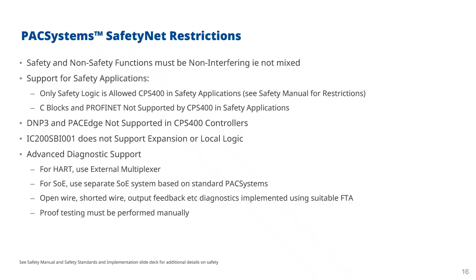If you want to do sequence of events, we do have some first up reporting capabilities inside the function blocks, but they're not normally timed. So if you wanted a full SOE system to do sequence of event reporting, then you would have to take your inputs into a separate SOE system, and that could be based on our standard PACSystems controller. Open wire, shorted wire, output feedback, other sorts of diagnostics, they can be implemented, but for that you have to use a suitable field terminal assembly.